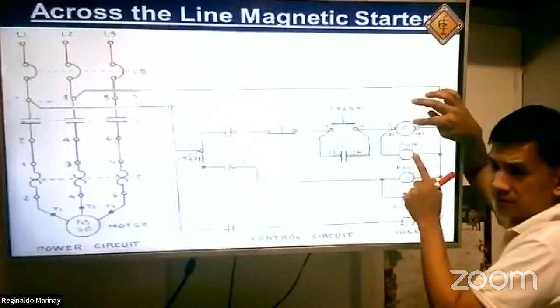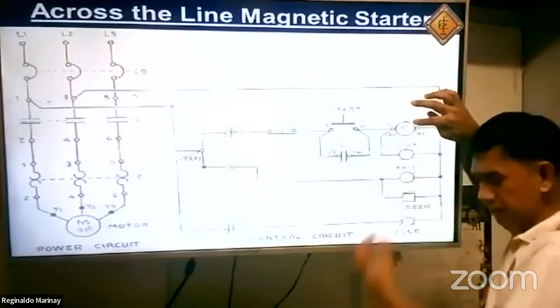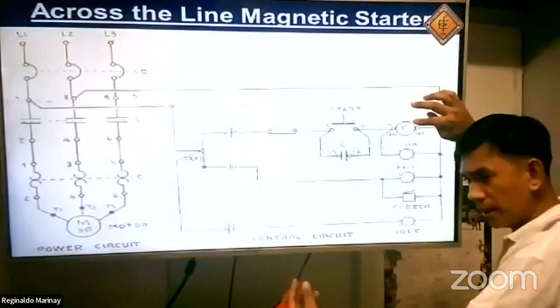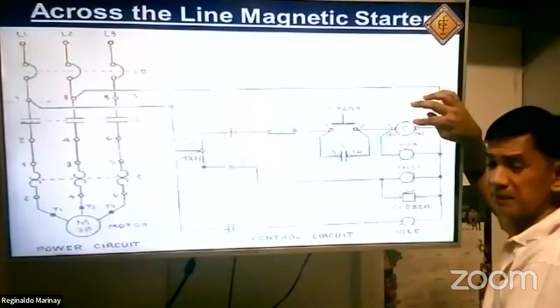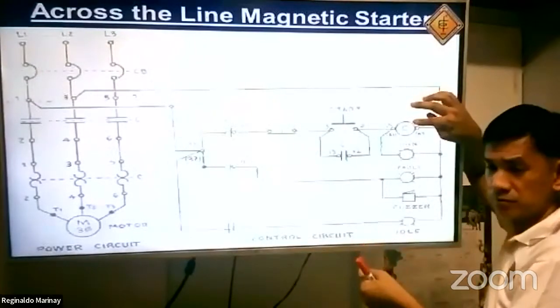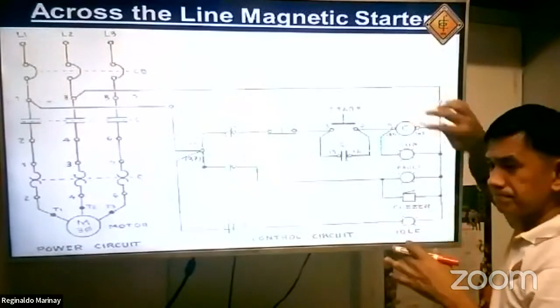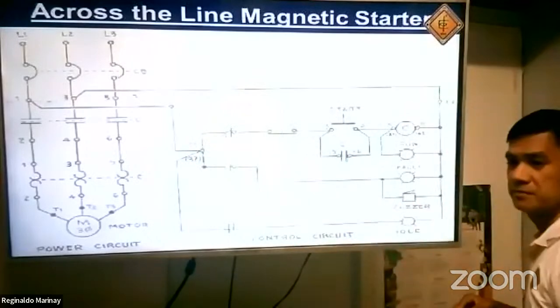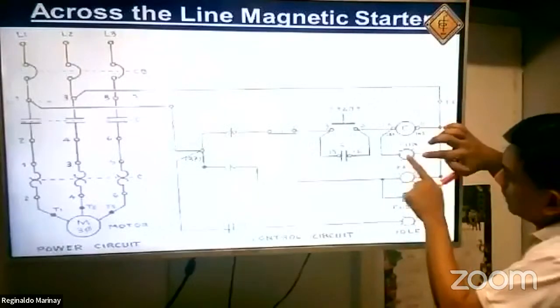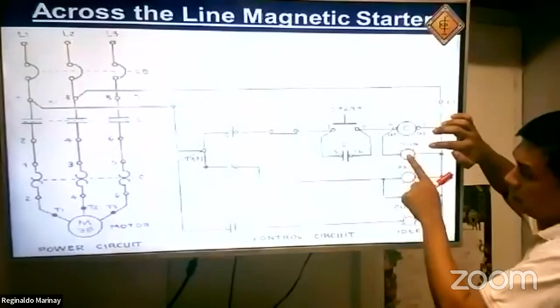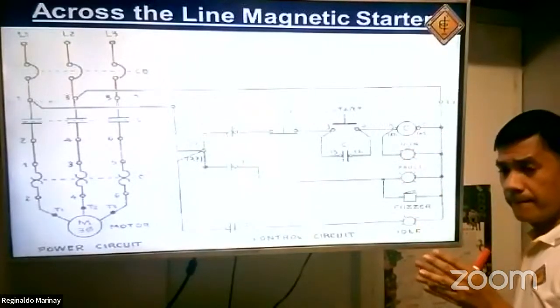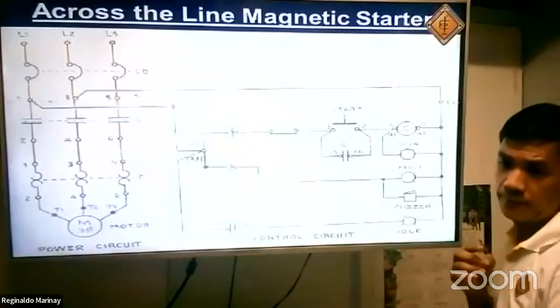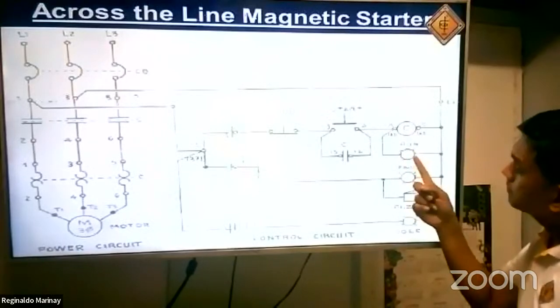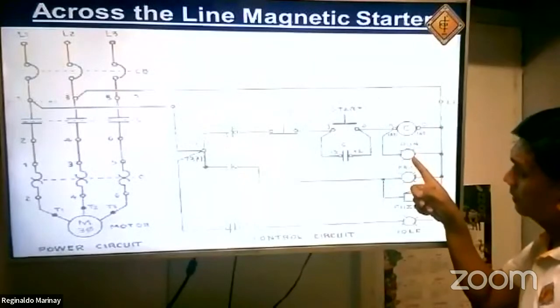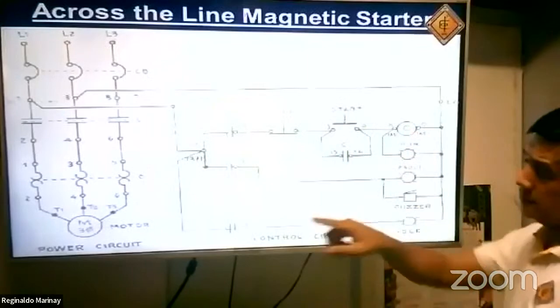Let's say this is color green. As you see, there is a color green now. The red one turned off, but the green one turns on, meaning you already know, even though that is 100 meters away from you, especially in the power plant. The motors are very far from the monitoring station, even hundreds of meters away. So take a look here. Say this is color green. At least you are aware that the motor is running, even though it is 200 meters away from you. Okay? See this one? So, once this becomes energized, these three will become closed. Okay? Then your motor now is running.